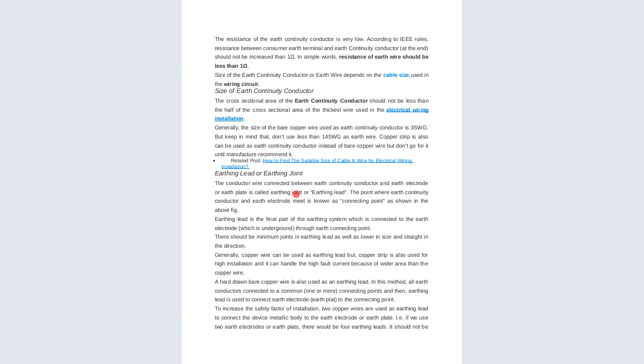So the earth lead, or the earthing joint. What is this? The conductor wire connected between the earth continuity conductor and the earth electrode or the earth plate is called the earthing lead. I showed you that in the diagram. The point where the earth continuity conductor and the earth electrode meet is known as the connecting point, as shown in the figure. So the earthing lead is the final part of the earthing system, which is connected to the earth rod, to the electrode, which is underground, through the earth connecting point.